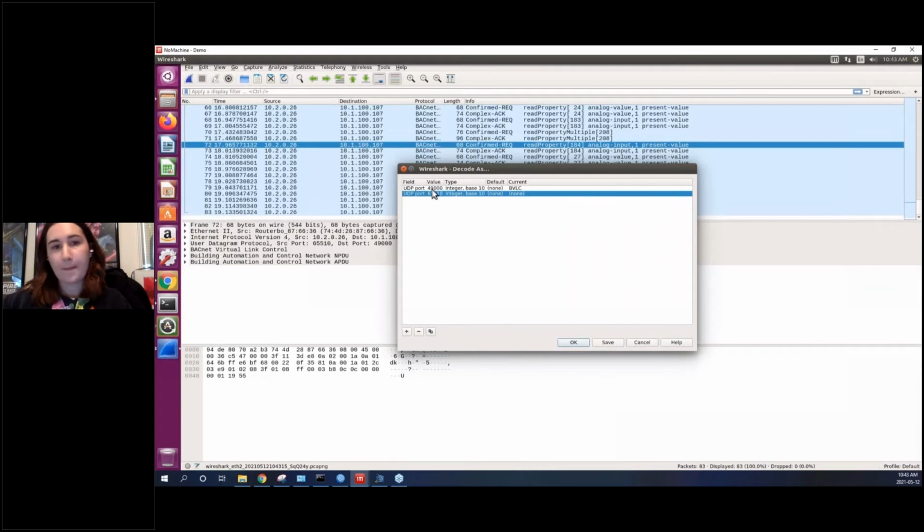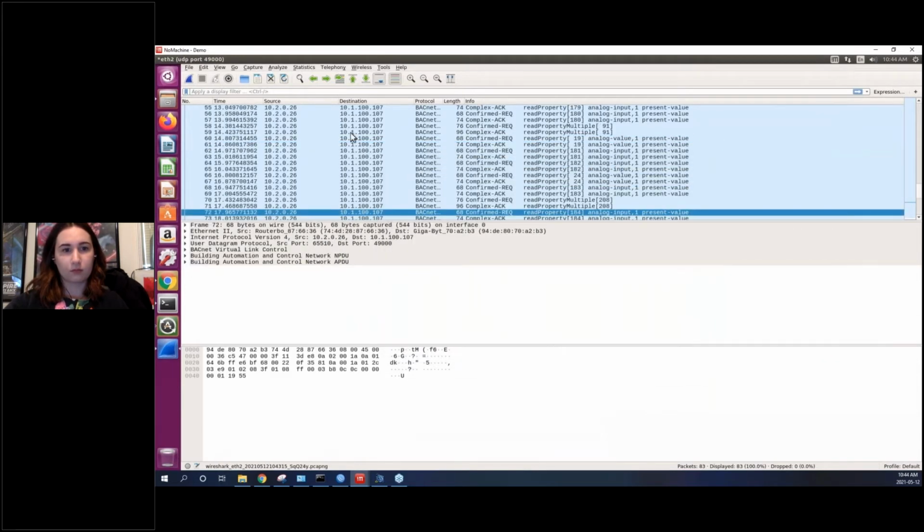And then we're going to configure that to be port 49,000 as we see here, and converting that to BACnet traffic or BVLC. So we're going to convert that to BACnet values. So that's how we're going to capture, and we can see here that we're already capturing all this information and we're getting this forwarded. So it is definitely circulating around our network.